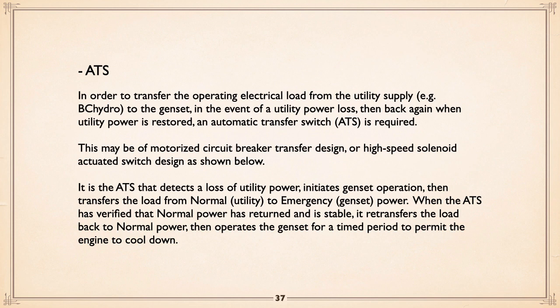Basically, you want to transfer the load from your utility to the generator in the event of a utility power loss, and then back again when utility power is restored. And for that, you need an automatic transfer switch, ATS. There are a couple of different ways of doing it. One is a motorized circuit breaker design, which can be either thermomagnetic breakers or strictly disconnect breakers. Obviously, a disconnect breaker is a little bit cheaper, but sometimes they believe in the actual thermomagnetic as a protection factor, okay? And there they have motorized.